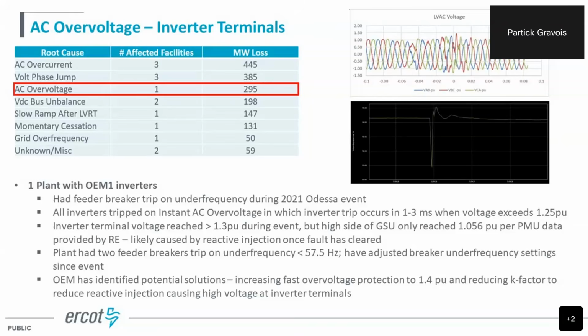They have adjusted that finally to provide that, you know, multi-cycle window. I think they put in like a 10-cycle window. So hopefully we won't see any more feeder breakers tripping. And as far as the overvoltage, there are a couple of things that they're working on. They are increasing the fast overvoltage protection to 1.4 per unit. So previously the OEM said they could not extend this. Now they're saying they can. So this is being jumped up from 1.25 to 1.4, but they will not be able to inject current above 1.25. So they will go into momentary cessation once that voltage goes above 1.25, but they won't trip unless it gets to 1.4. They're also reducing the K factor to reduce the reactive injection.